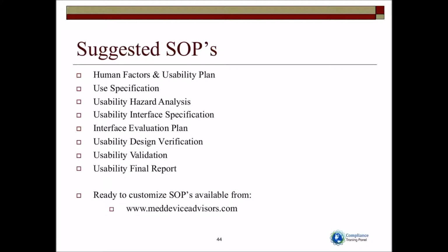SOPs for human factors, there should be a separate SOP for each of these, the plan, the use specification, the hazard analysis, the interface specification, the evaluation plan, the design verification, validation, and an SOP for a final report.